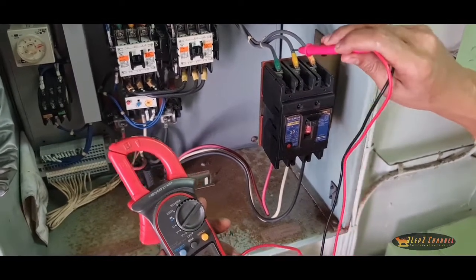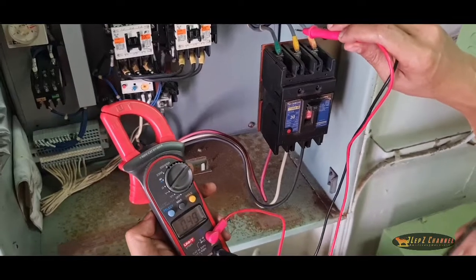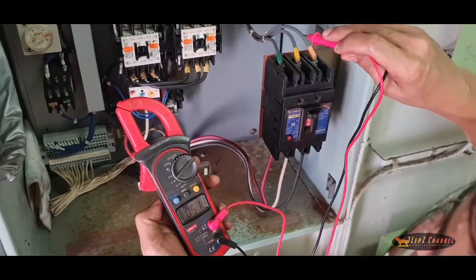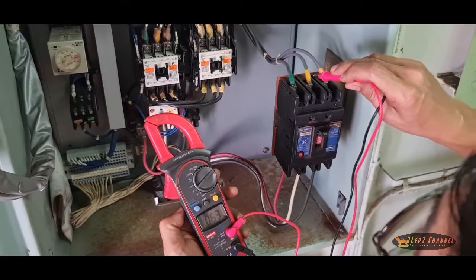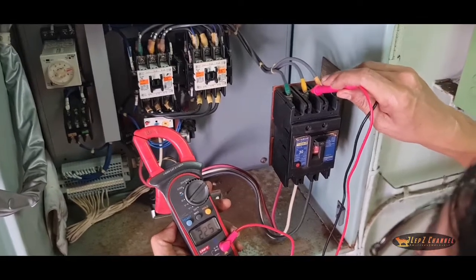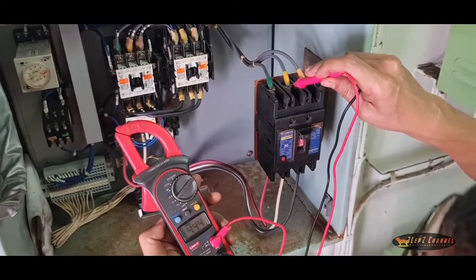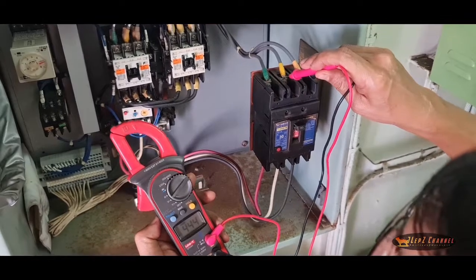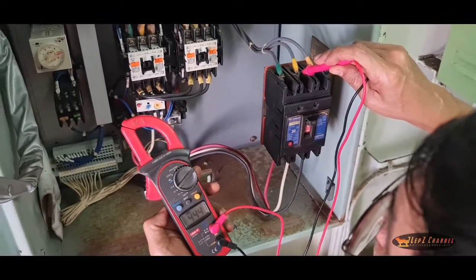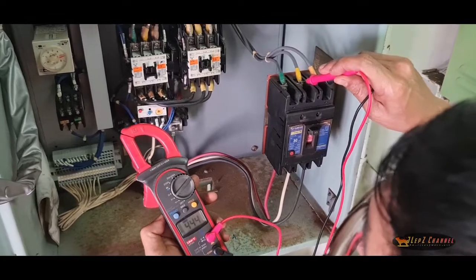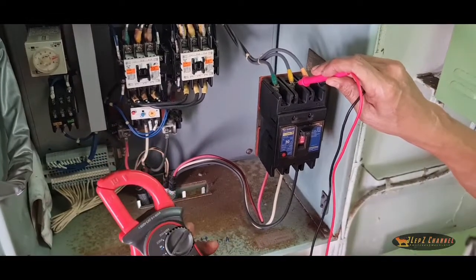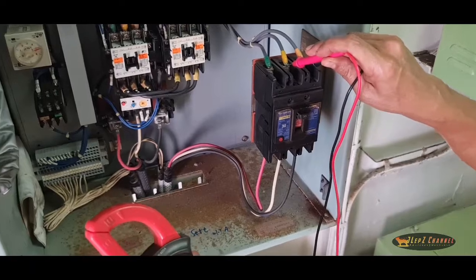Now we want to test the line voltage between line 2 and line 3. Our reading is 444. So the voltage supply of the engine room fan is very good, in the range of 440 volts.